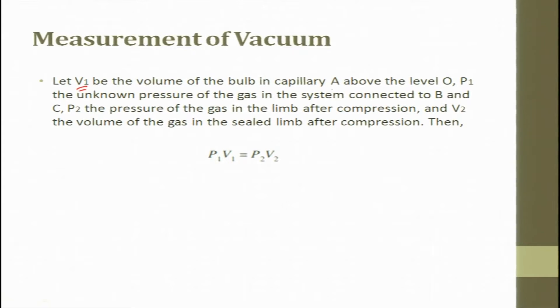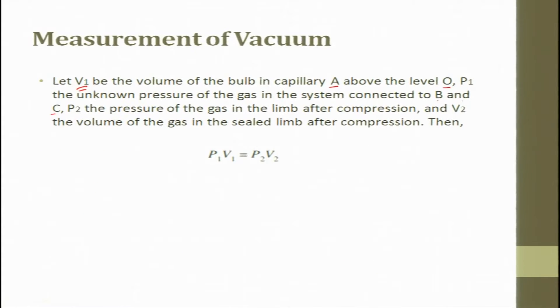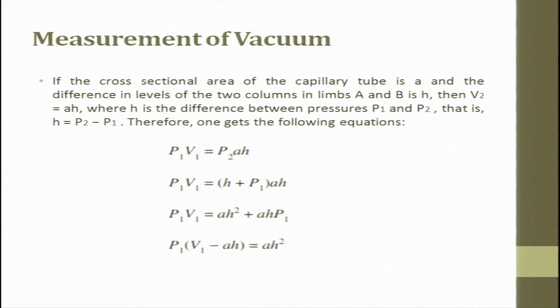If V1 is the volume of the bulb in capillary A above level O, P1 is the unknown pressure of the gas in the system connected to B and C, P2 is the pressure of the gas in the limb after compression, and V2 is the volume of the gas in the sealed limb after compression, then P1V1 = P2V2. If the cross-sectional area of the capillary tube is A and the difference in the level of the two columns in limbs A and B is H, then V2 = A × H.